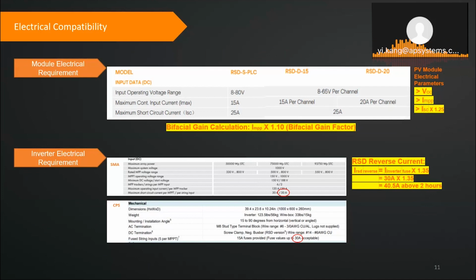That can be done in a number of different ways. The inverter can be placed within 1 meter of the array. If that is possible, then you do not need any additional rapid shutdown, since the inverter itself will be the rapid shutdown. Alternatively, a rapid shutdown box can be used. There are a few options out there. I think the Fronius rapid shutdown box is the only product out there that I'm aware of, and that's a 600 volt only solution. And if neither one of those is the case, then you need module level shutdown with products such as the AP Smart. And then you'd place those on the back of each module.